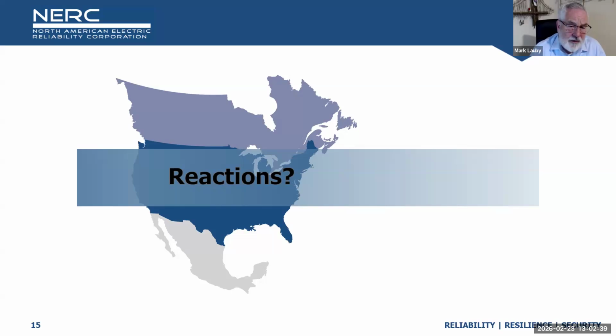And we basically put a number out there and said, show us when we're wrong. Just like when I started in 2007, we said 15% reserve margin for thermal systems and 10% for hydro. If yours is different, give me a different number. Otherwise, that's what we're going to say. Below 15%, you're in trouble. Below 10% on hydro, you're in trouble as far as reserve margins. And that was a rule of thumb we used back when I was in MAP. Does that get to your question?